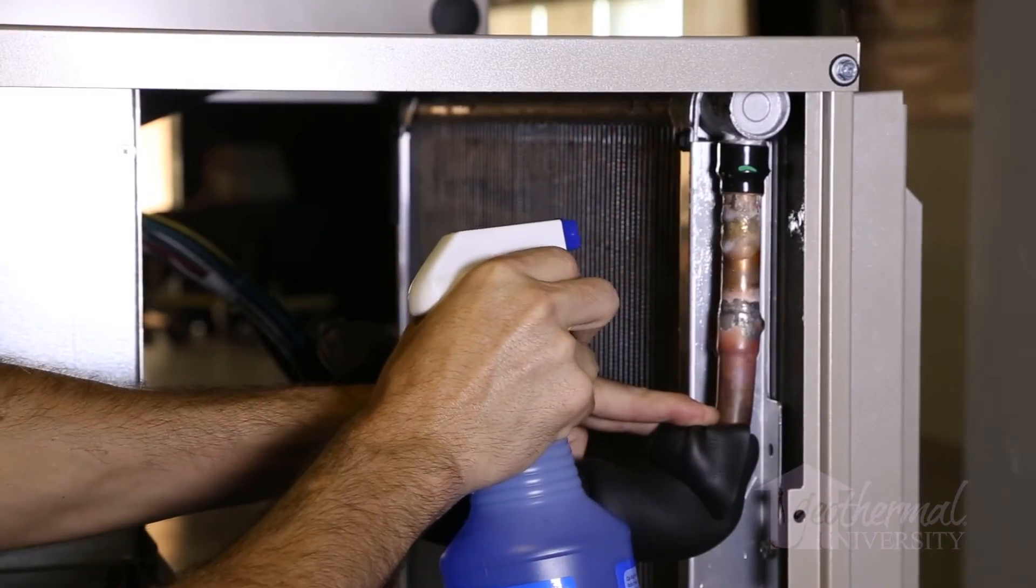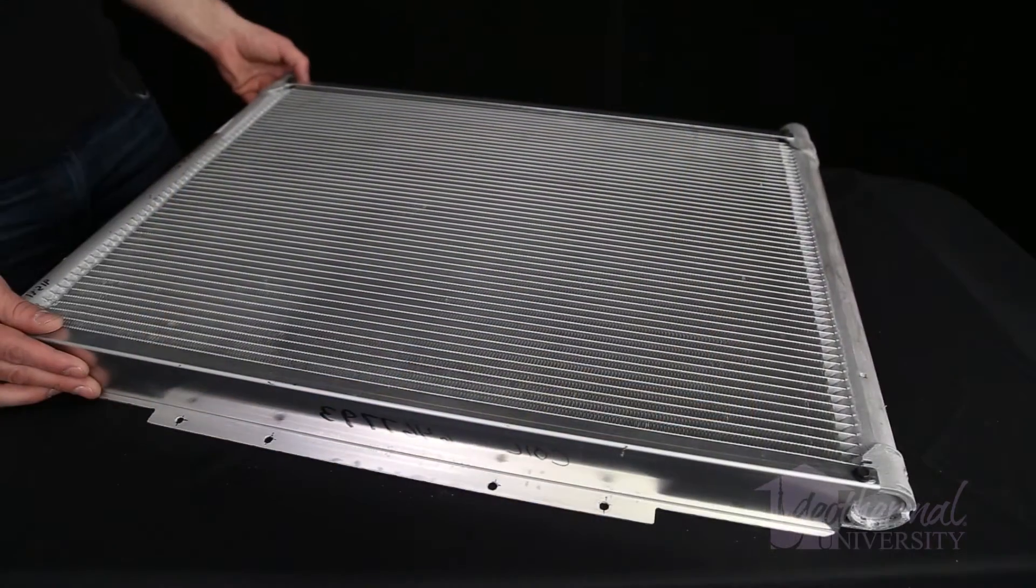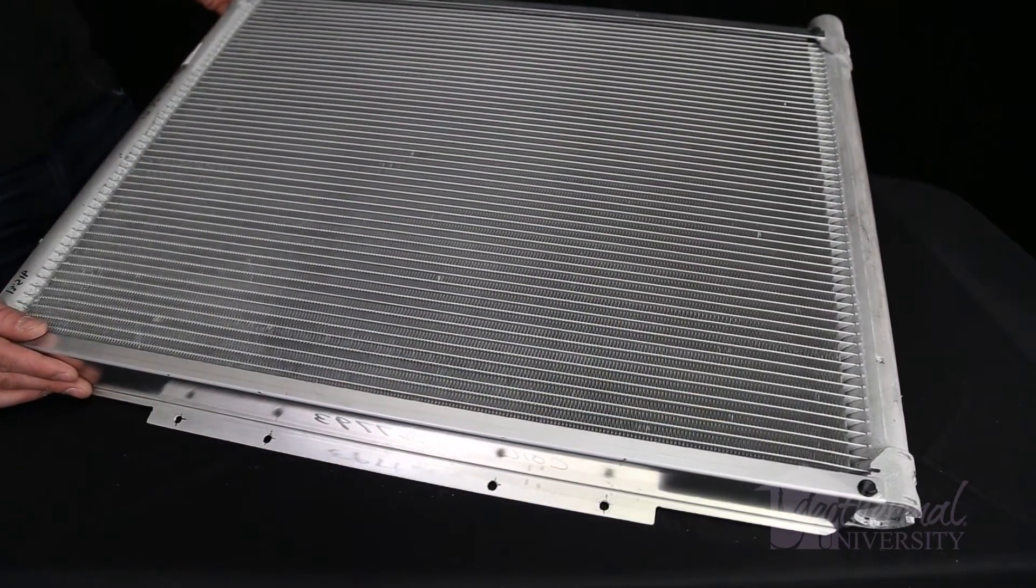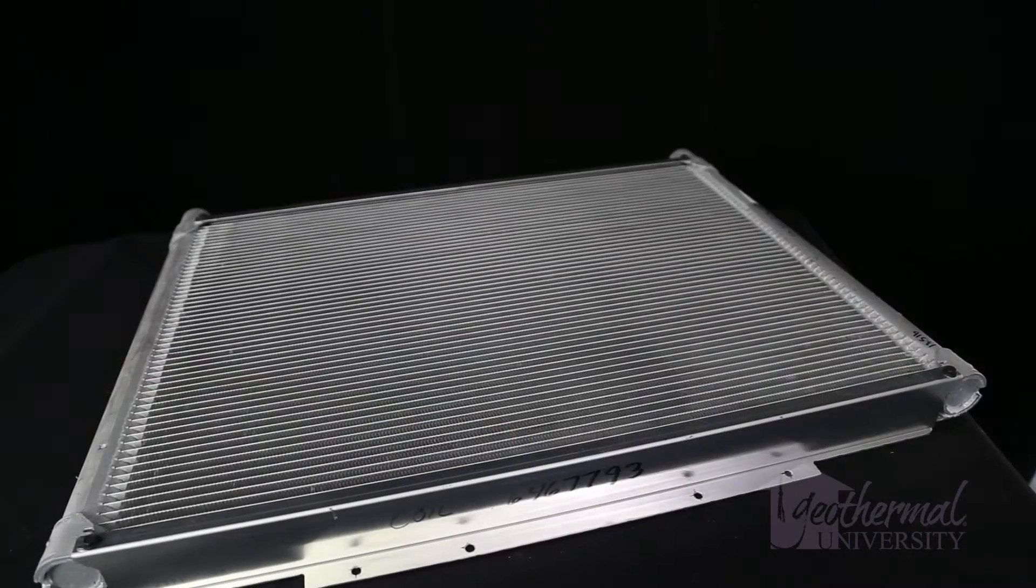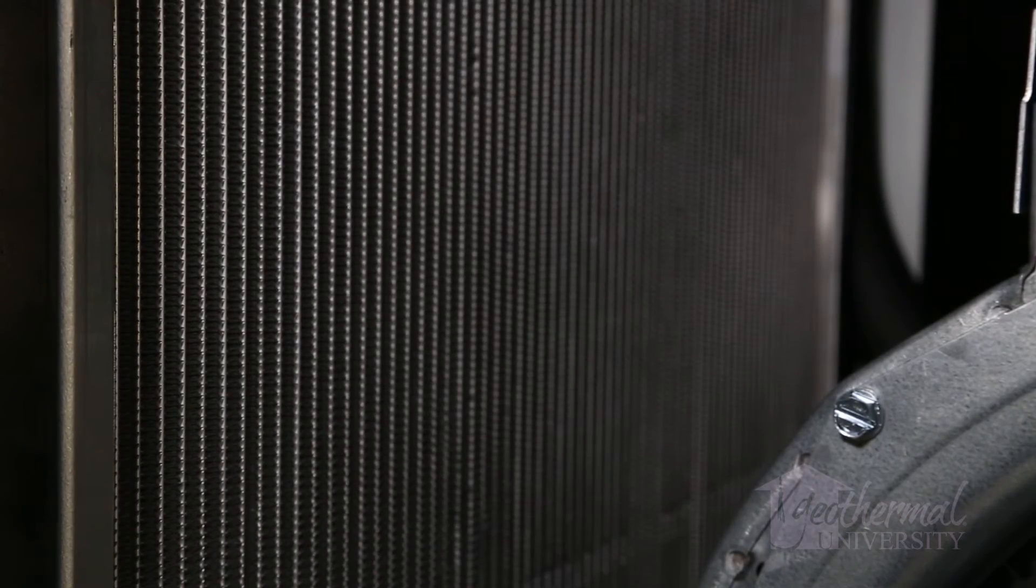It is important to pinpoint the leak because sometimes a repair is a better option than replace. Depending on the leak rate, a more thorough investigation of the coil slab distribution circuit and return bends may be needed.